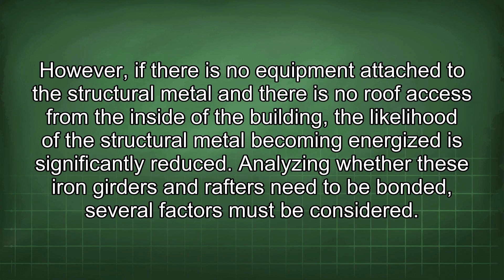Analyzing whether these iron girders and rafters need to be bonded, several factors must be considered. First, the code definition of exposed indicates that if the metal is not permanently enclosed and is accessible, it is considered exposed. Second, the requirement for bonding arises if the structural metal is likely to become energized. Third, if there is no equipment attached to the metal and no easy access that could lead to accidental energization, the necessity for bonding is less apparent.